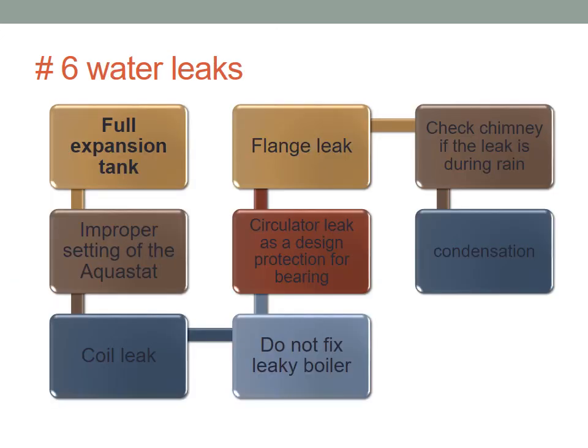Okay. If we have water leaks, make sure that the expansion tank is sized correctly. Also, the improper setting of the aquastat. What does that mean? If the setting of the aquastat is too high, above 180 or 212, and the system is designed for hot water, you might be expanding the water too much or building pressure, which means water will leak at some point. Coil leaks are very possible when it's corroded inside a boiler or a water tank.